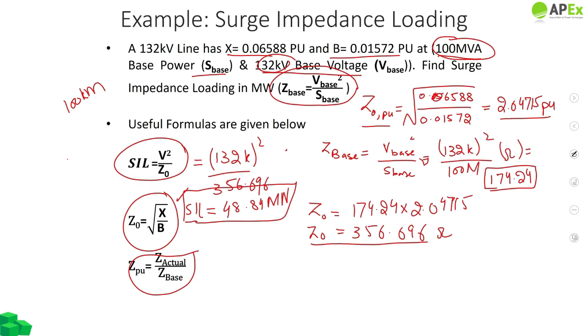So what does this signify? When the line is loaded at the surge impedance loading of 48.84 MW, the sending end voltage and the receiving end voltage would be the same. But if the line is loaded below the SIL, the receiving end voltage would increase. Conversely, if loaded above 48.84, the receiving end voltage would substantially decrease. We will try to prove this using the simulations shown in the coming slides.